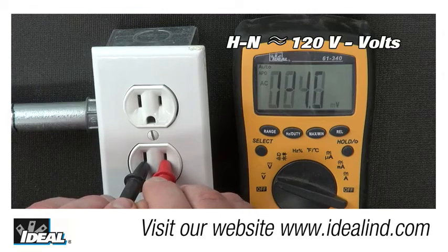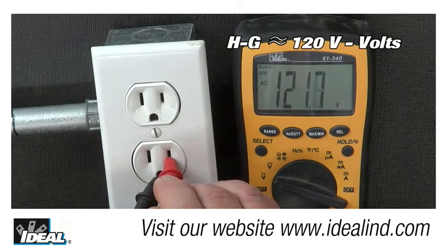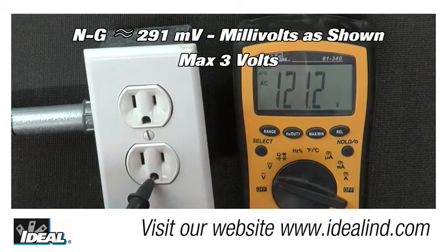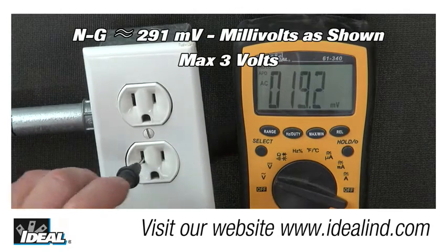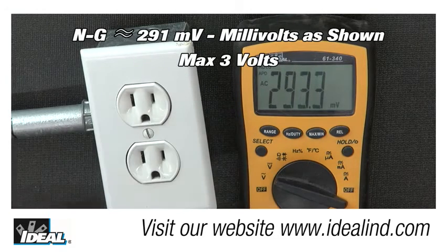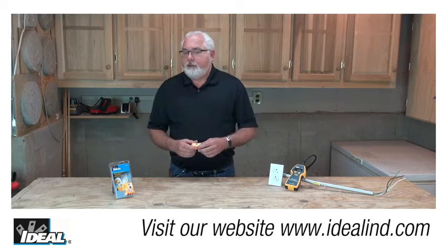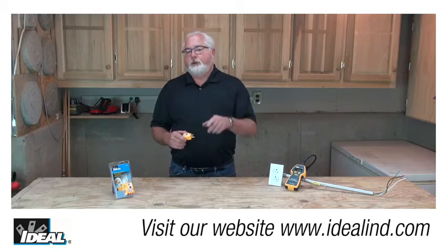And there should be about 120 volts hot to neutral and 120 volts hot to ground. And neutral to ground should measure no more than about 3 volts. And neutral to ground voltages greater than 3 volts at normal power frequencies are indicative of a wiring problem and should be investigated. Receptacle testers also can be used to trip a GFCI receptacle to ensure that it's working properly.